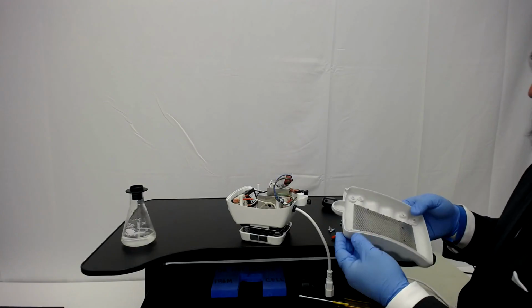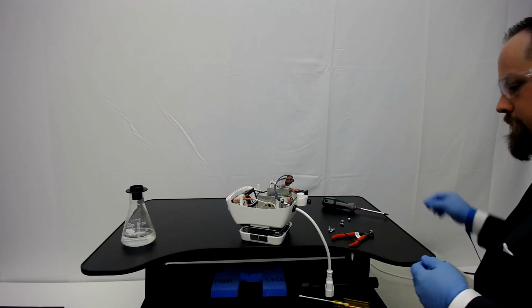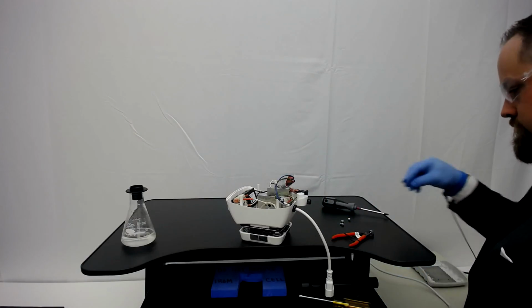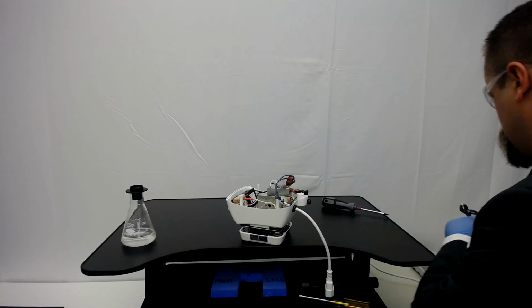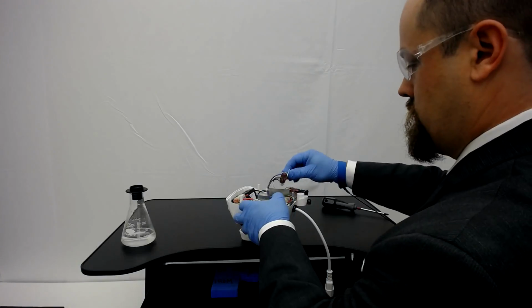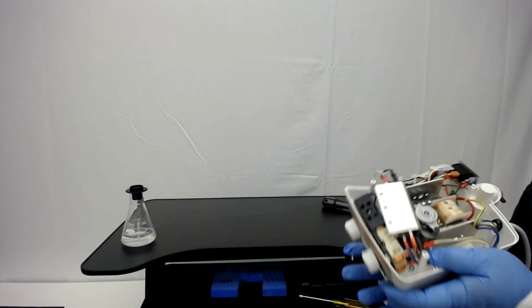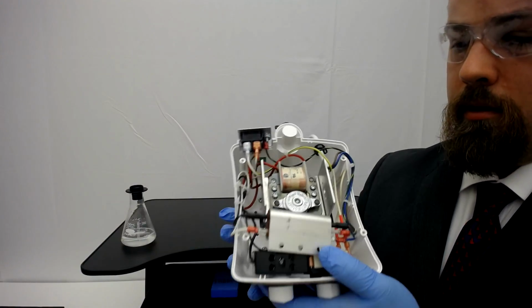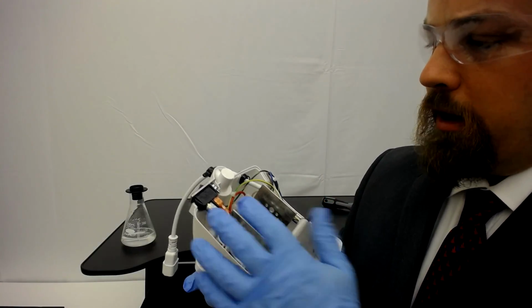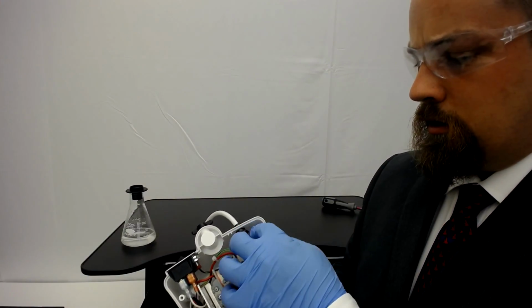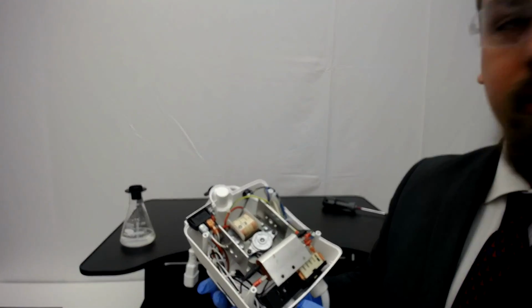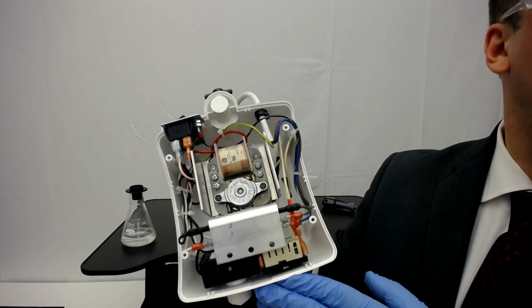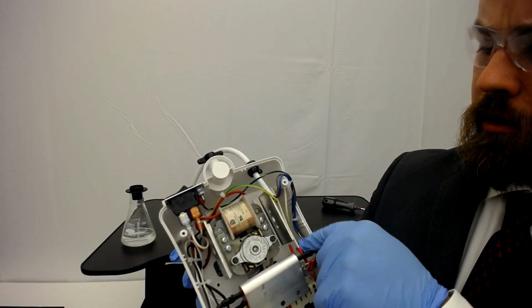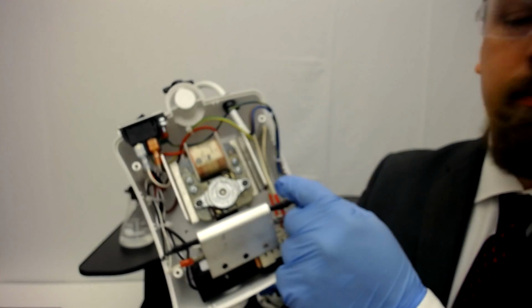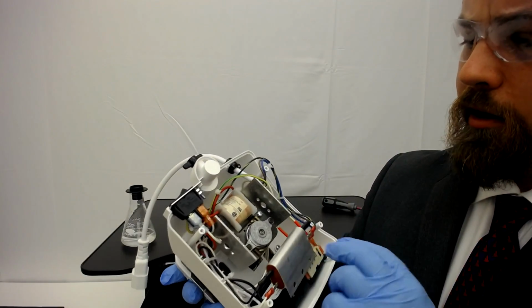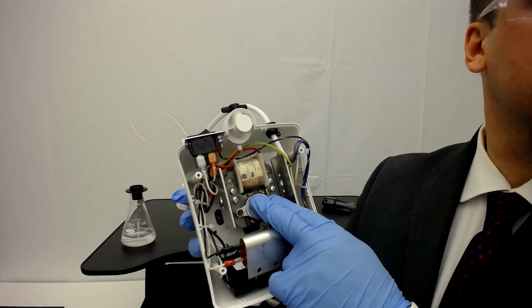All right. The base plate can be taken off and set aside along with the screws. And here we have the inside of the unit. What you want to make sure at this point, just do a check of everything on the unit. Make sure that the wire routing is going down the side of the unit. None of the wiring is damaged, and that the wiring is out of the way of the motor.